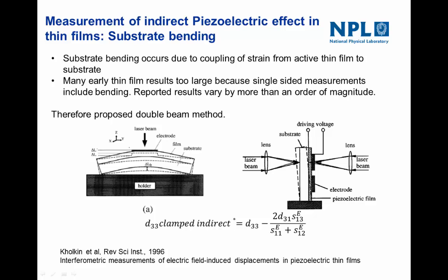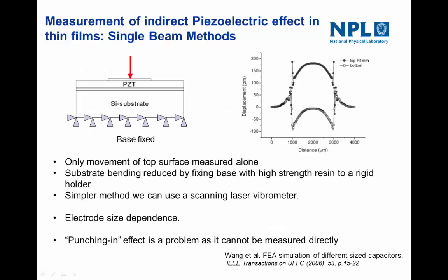People were measuring the top surface movement and assuming the base was completely fixed, which is not the case. So Kholkin came up with the idea of using a double beam interferometer to measure the change in thickness of the sample. The double beam laser system uses a laser on each side to measure the change in thickness, and it doesn't matter how the sample moves or bends. However, as we've seen, when the sample is allowed to move laterally the silicon will also contract, so Kholkin's standard equation is actually incorrect for the double beam system — we need to use the corrected one from the previous slide.